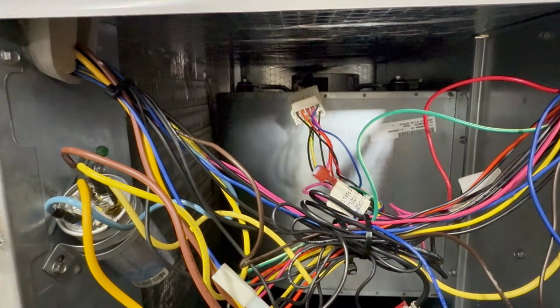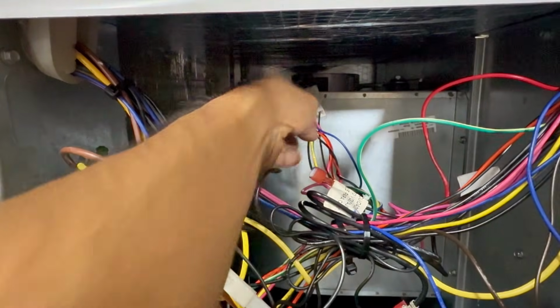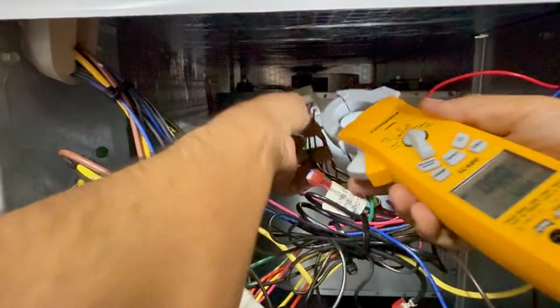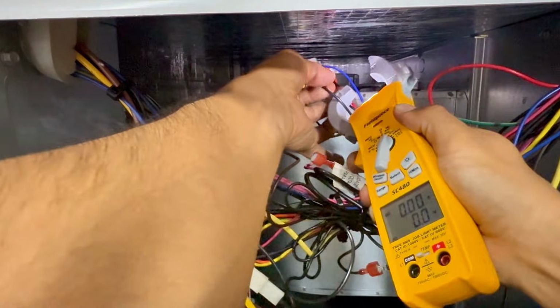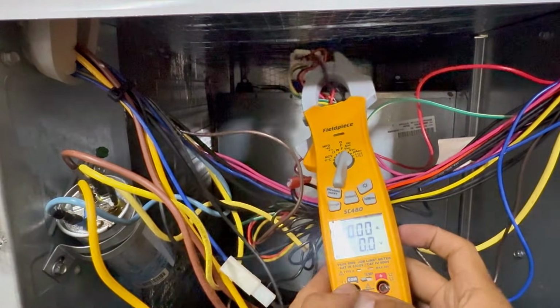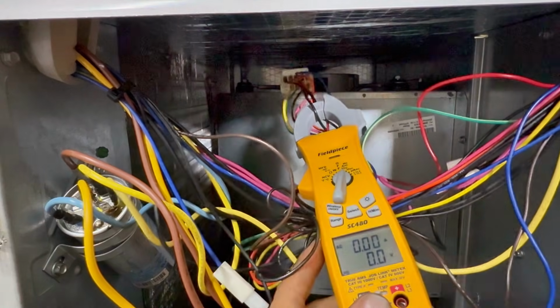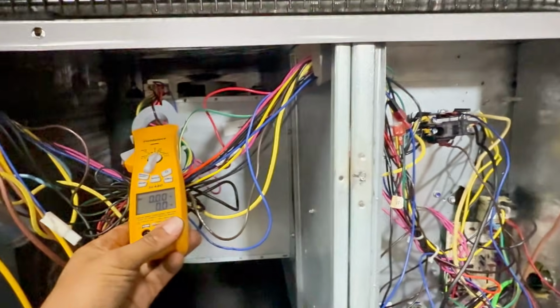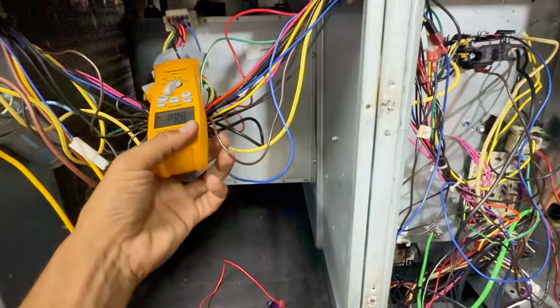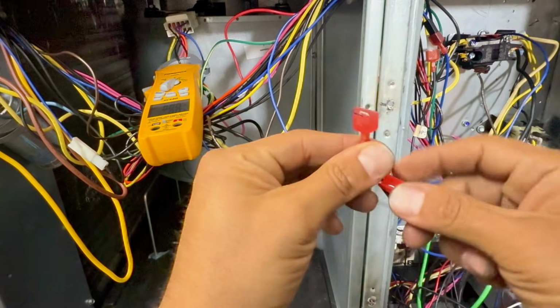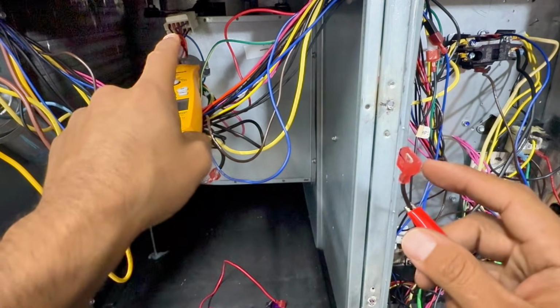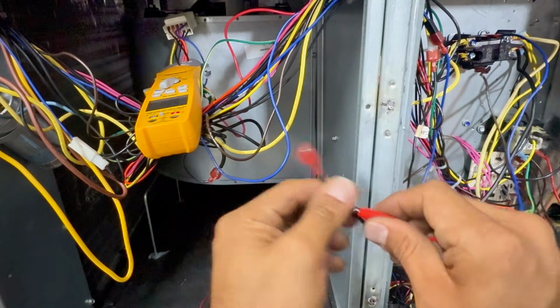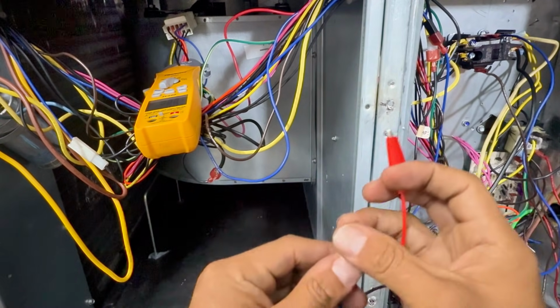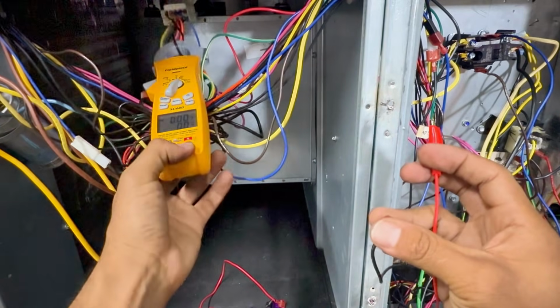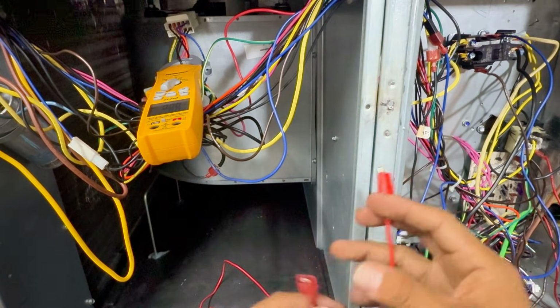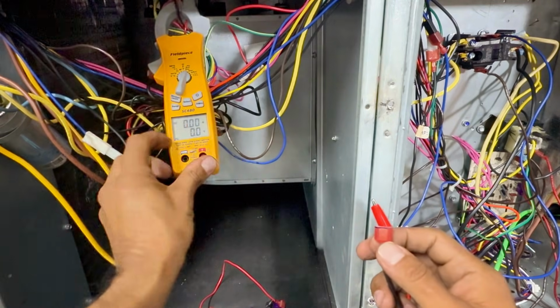So I'm gonna go ahead and put it on amp draw, right? And I'm gonna go ahead and get the black wire that I had mentioned. This black wire, just put it around 1, okay? And look, I have zero amps. There's nothing going on. Okay, so now I'm gonna go ahead and locate the wire. So this wire here goes to that black 24 volt speed tap. So I have raw 24 volts right here. And I have a video on ECM, so feel free to go to my channel to check it out on how to diagnose them. But you see 0 amps.